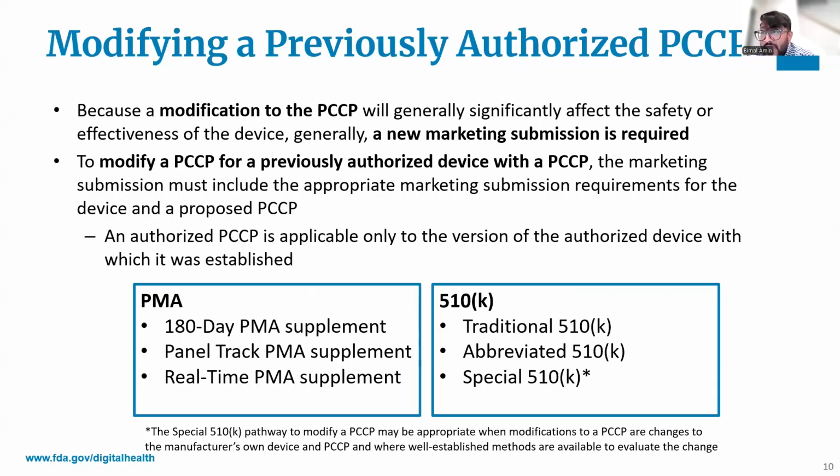The special 510(k) pathway may be appropriate when the changes to the PCCP involve your own device and your own PCCP, and where well-established methods are available to evaluate the change. The key takeaway here is that PCCPs are a living document. It can evolve, but changes to it are still subject to FDA review. It's not a one-time approval that gives you unlimited flexibility forever.